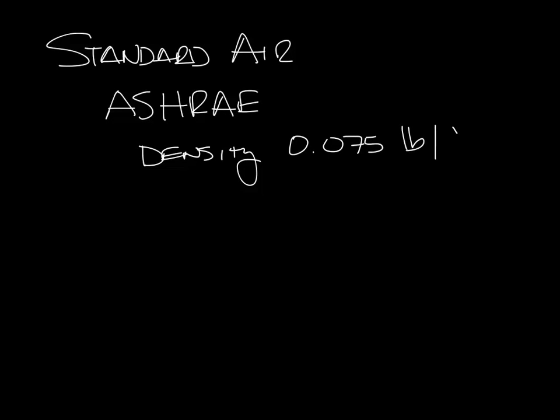So standard air is defined by ASHRAE as having a density of 0.075 pounds per cubic foot, a barometric pressure of 29.92 inches of mercury at sea level, and 70 degree dry bulb temperature.